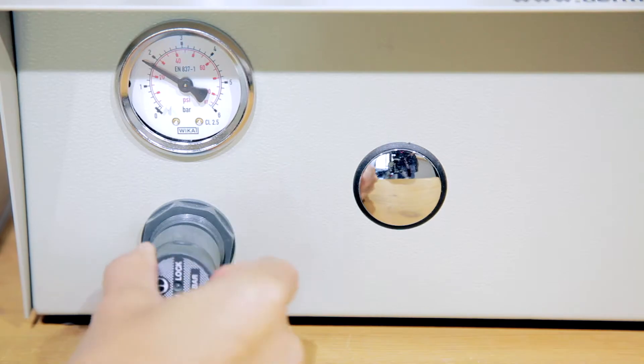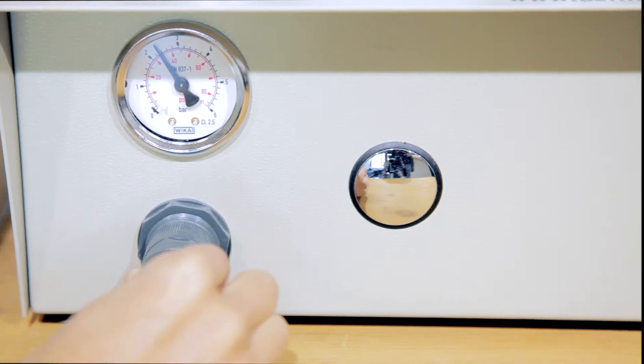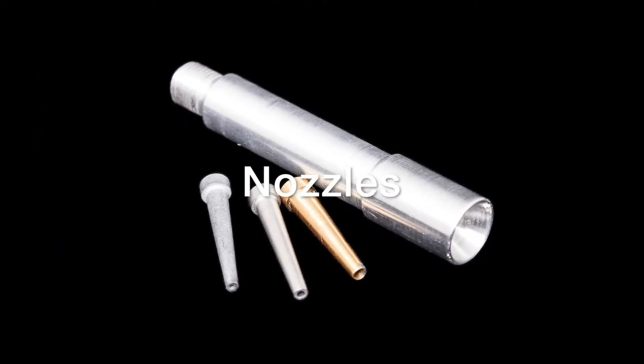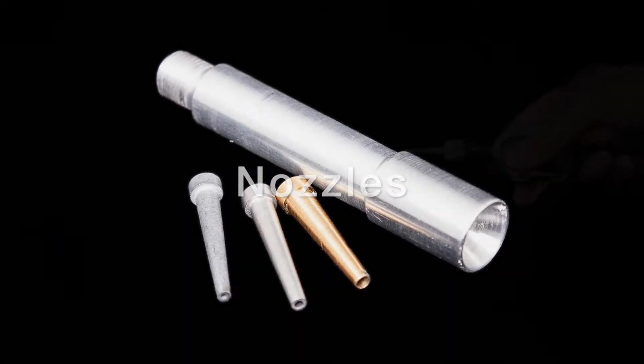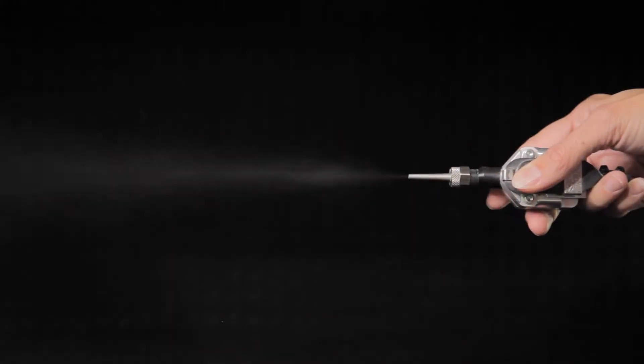After filling, the pressure, depending on the individual object, should be set to 1.8 to 2.2 bar. The air blaster supports four different nozzles. The nozzles differ in diameter, which in turn defines the amount of particles blown through the nozzle.